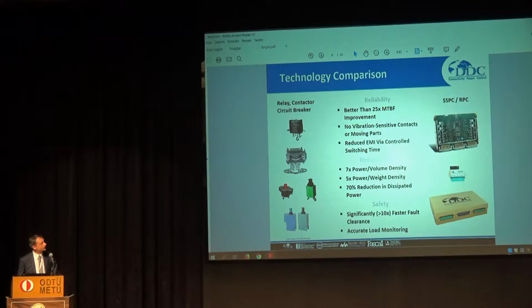What does that bring in terms of benefit? In terms of reliability, a solid-state power controller is 25 times better or improved in terms of the MTBF compared to a common mechanical circuit breaker. These devices are not vibration sensitive because there are no moving parts inside, so very important for land-based applications where you have a harsh environment, a lot of vibrations, shock, where circuit breakers could fail. Solid-state power controllers are not affected by this. You have reduced EMI because we control the switching times, switch on as well as switch off, which you cannot do with a mechanical breaker.